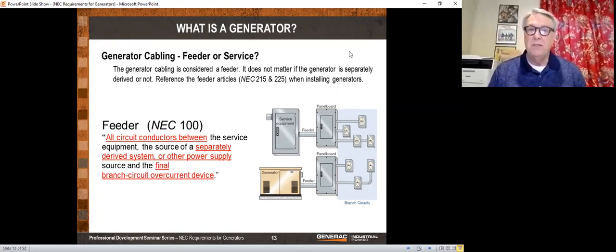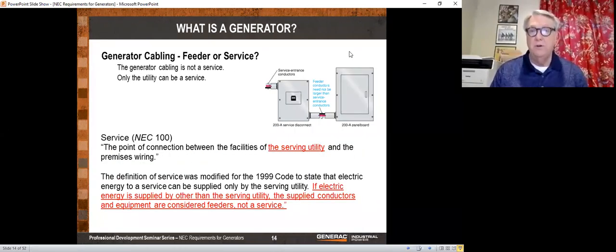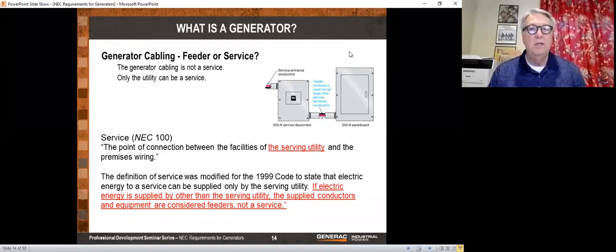And then the service is the utility. It's where you connect into utility. Anything between those two is a feeder. So basically, between the service entrance and the panel board would be a feeder. Now, all generator cabling is a feeder. It is not a service. Why is that? Well, let's look here. NEC 100, again, this is the definition section. It says the service is the point of connection between the facilities of the serving utility and the premises wiring.